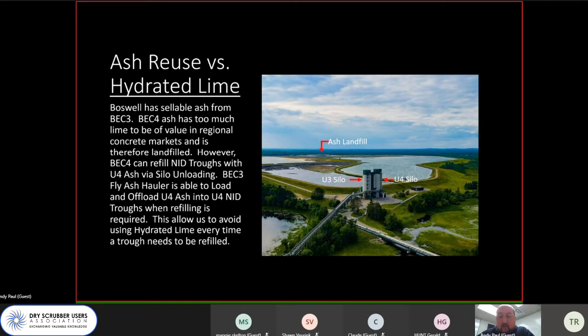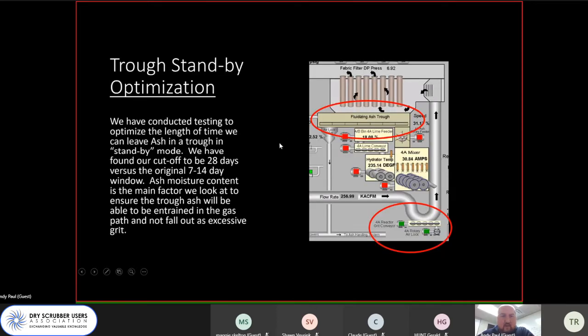Another thing we've worked to do, to allow us to empty out the Unit 4 silo on longer outages, is a lot of trial and error and testing to verify we can keep that ash in our troughs. We've really used moisture content for this. Originally we had a 7 to 14 day window, and we've expanded that to 28 days that we can maintain ash in the trough without emptying and refilling it. So there's a cost savings in not buying hydrated lime, not paying the ash vendor to load ash in here, and it also gives us the opportunity to do maintenance on our silo during longer outages. It's been a pretty good effort for us.